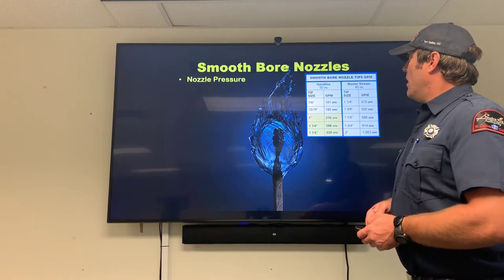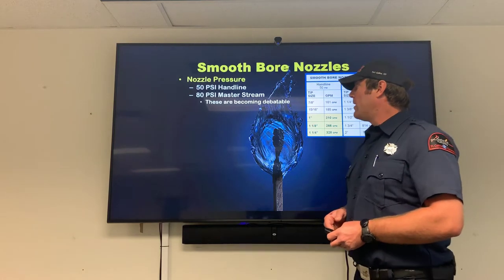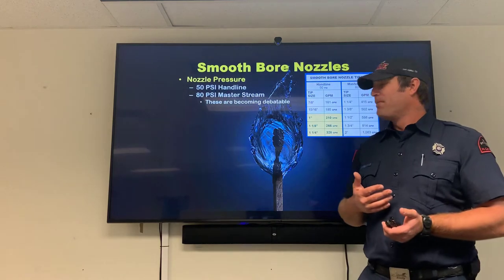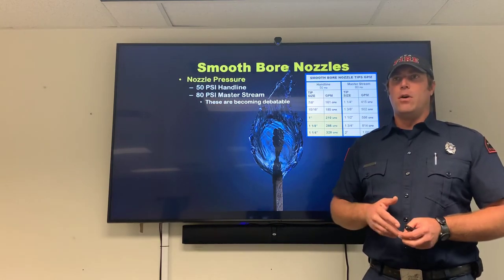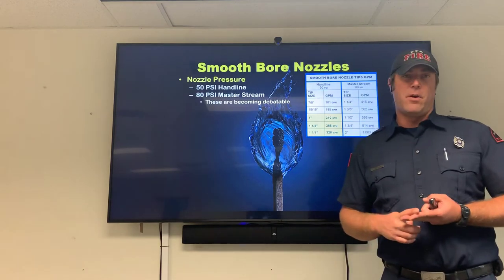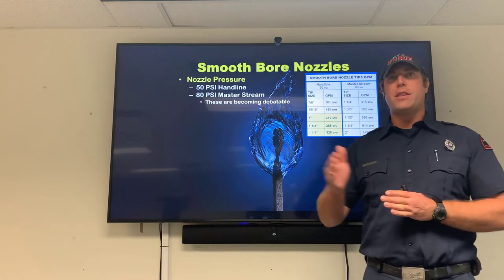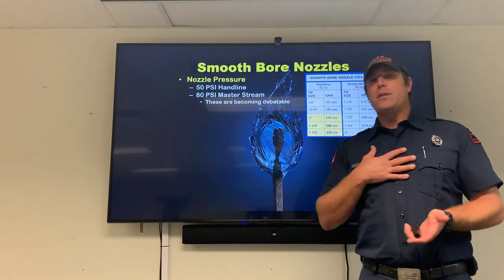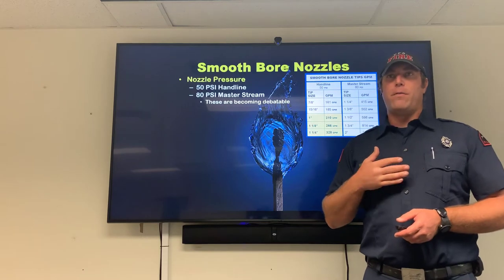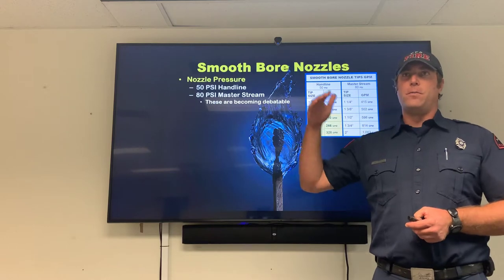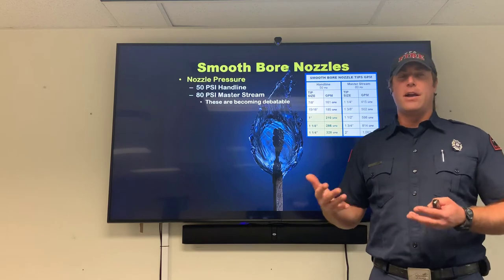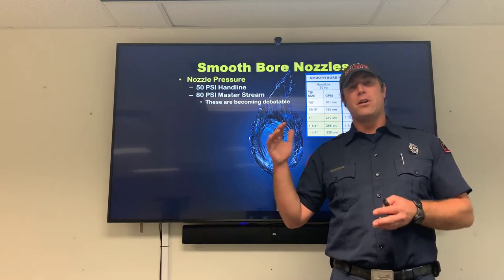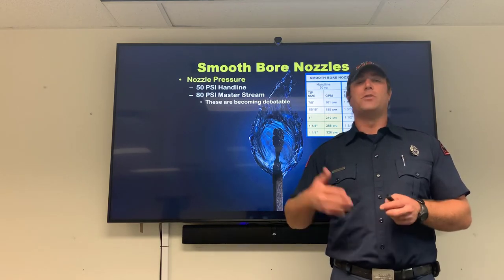Moving on to smoothbore nozzles: nozzle pressure is typically 50 PSI for a handline and 80 PSI for a master stream, though these are becoming debatable. Some departments are going to an inch and three-sixteenths tip and treating it more like an automatic nozzle, pumping a little hot or a little light depending on need. At PFA we have an example in our high-rise pack where we opted for 45 PSI nozzle pressure on an inch-and-an-eighth tip, bringing flow from 266 down to 252 GPM to match what the standpipe is designed to provide.